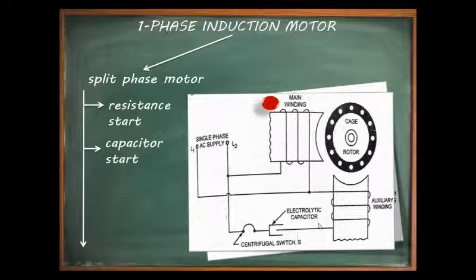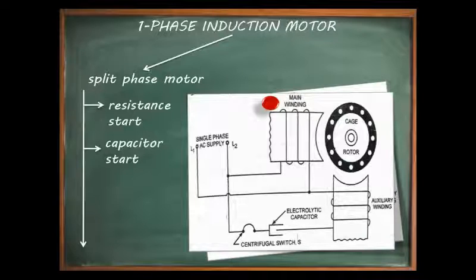The second type of single phase induction motor is the capacitor start single phase induction motor, also called the capacitor start induction run motor. Its construction is similar to the resistance start motor, except that the resistance is replaced by a capacitor. At starting, the phase split between the main winding and auxiliary winding is 90 degrees. Like the resistance start motor, the starting winding is disconnected by a centrifugal switch as the motor picks up speed.